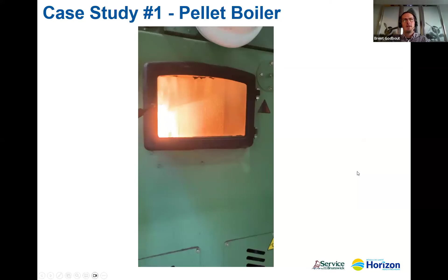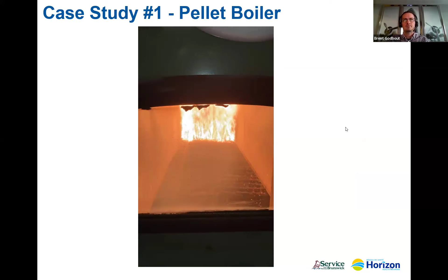So there's the firewall at one end of the boiler with the pellets. The ash all comes down this conveyor belt. All that combustion gases and heat go up into the upper part of the combustion chamber and gets transferred to the hot water tubes that are above this. That hot water goes over to the hospital, goes into a heat exchanger where it gets exchanged into the hot water loop, or the heating loop of the hospital.